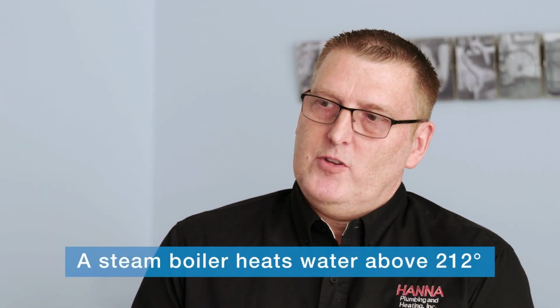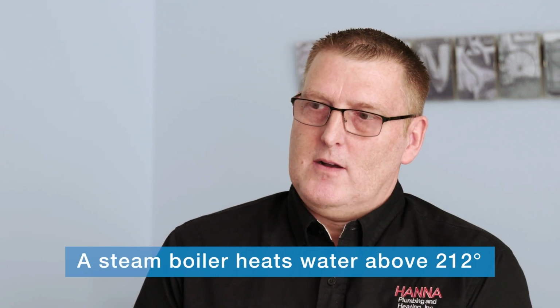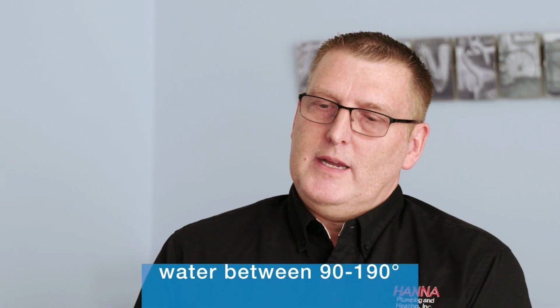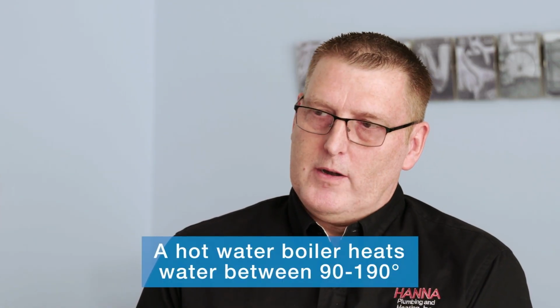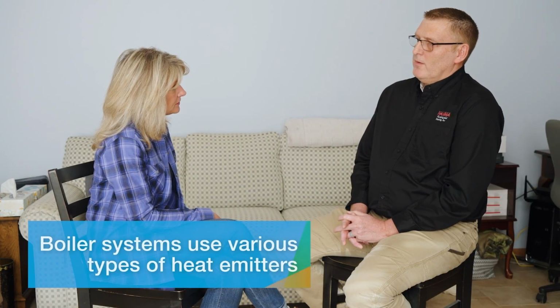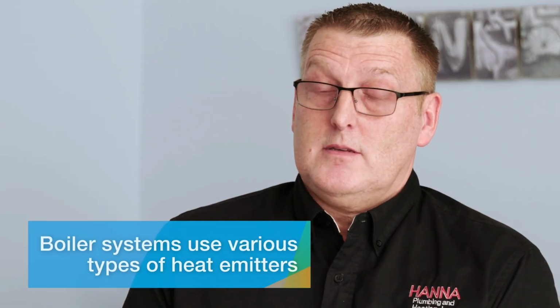Hi, Bill. Hi. Can you explain to us the difference between a hot water and a steam boiler? A steam boiler takes hot water and heats it up to above 212 degrees, and then it distributes that throughout the house, and it condensates and goes back to the boiler to start the cycle over again. It's not that efficient for a home to do that because it's heating way beyond the means of desired temperature for the house. With a hot water boiler, you're heating up between 90 to 190 degrees of water, which is more usable water. Homes have various types of heat emitters, such as radiant baseboard, radiant floor, radiators, indirect water heaters, and they even have snow melt systems that you can do outside.